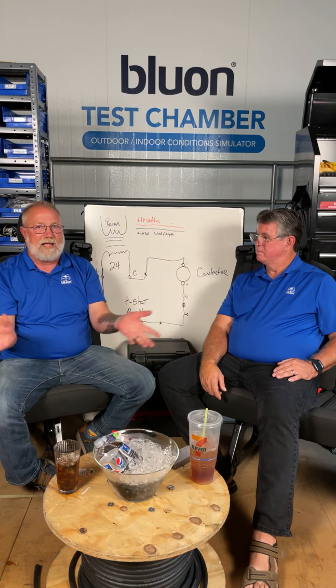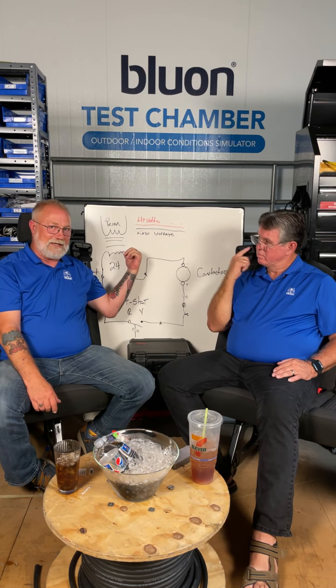Yep. And going back to earlier, which brought us into this whole control piece, remember when you're taking the step from residential and light commercial and you're going to that Trane, oh my gosh, open up the doors, relays, wires, all the same color. Start at the same point, guys. Turn the thermostat on, turn the fan switch on, open up that big panel, ignore all the black wires, ignore all the gray relays, find the transformer, and see if you have primary voltage, see if you've got secondary voltage. Then go from there.